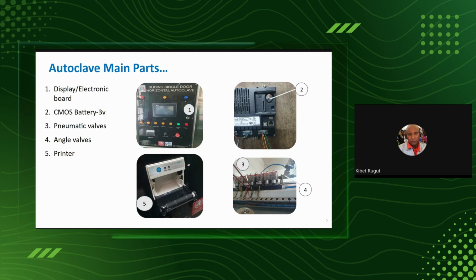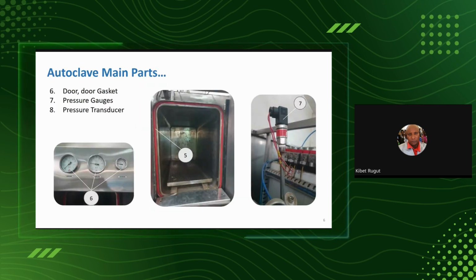There are pneumatic valves in these autoclaves. Why? Because you have to open certain valves at the right time, and these are high pressure, so they may not simply be valves that you want to operate using bare hands, because there is very, very high temperature steam moving from one part to another. And then valves which are manual, and then a printer which monitors or records the cycle temperatures. Again, we also have other parts that are important.